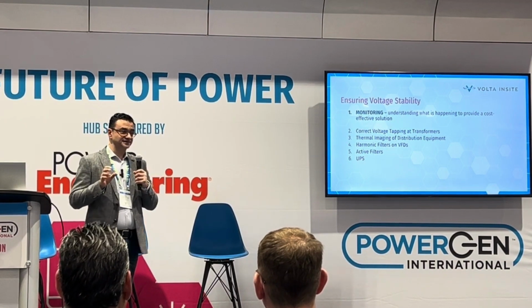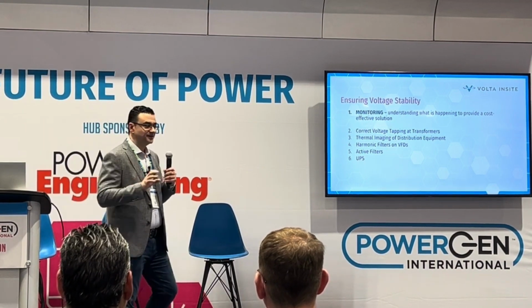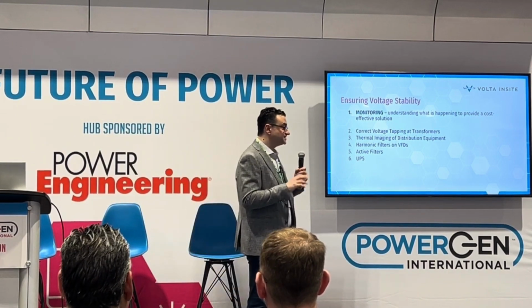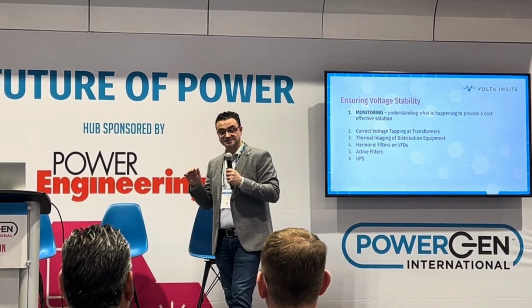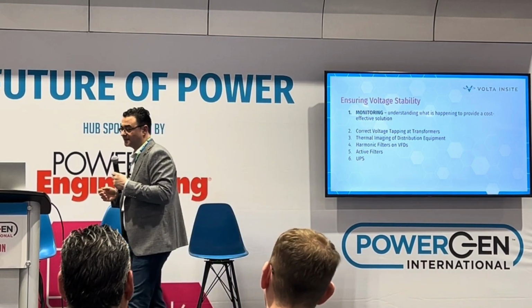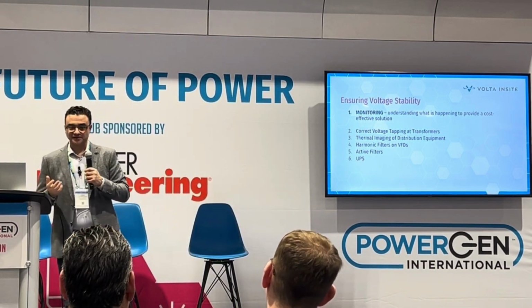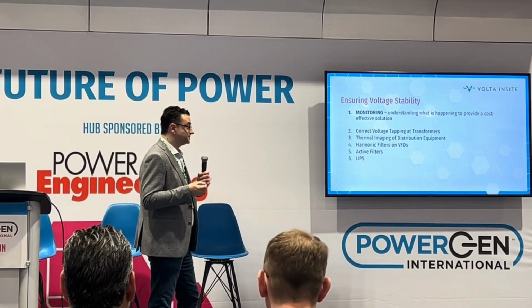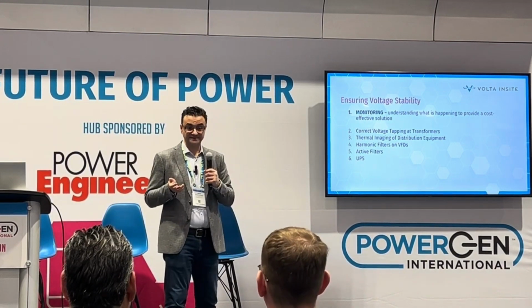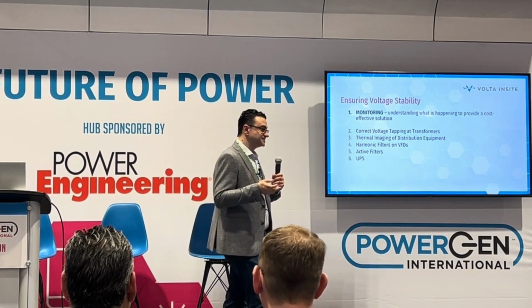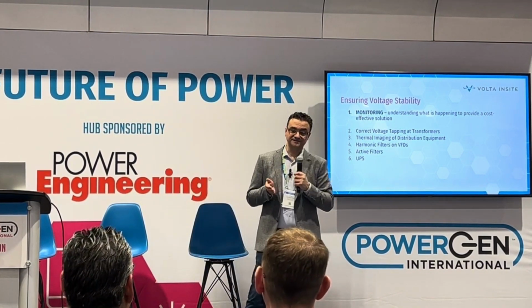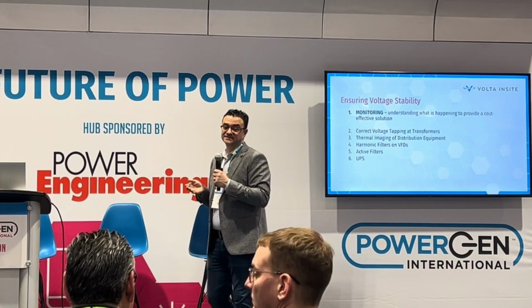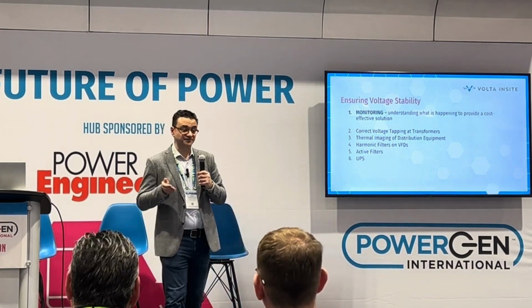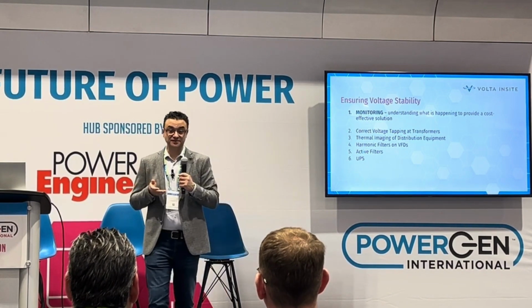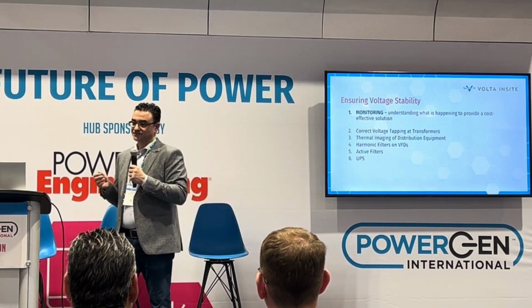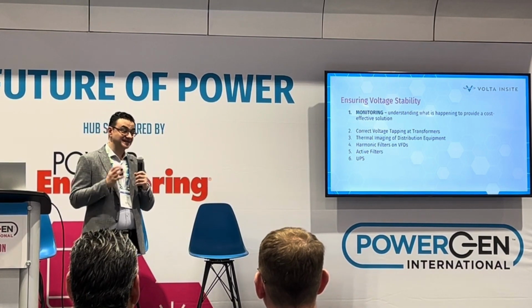So we were able to solve that problem with a simple $200 isolation transformer that maintained constant voltage, and the VFD started running up. The reason I tell this story is that I was called in by the director of maintenance for this facility, and his concern was that the electrical contractor that deployed the VFD had come back and wanted to sell them a big $200,000 power filter to fix the problem, without any guarantees. So if you have data, you can potentially save a lot of money.